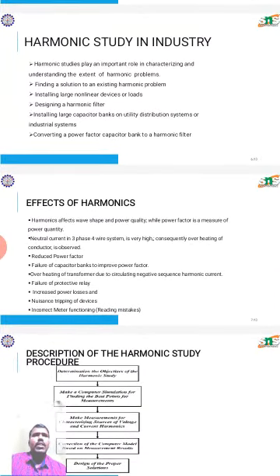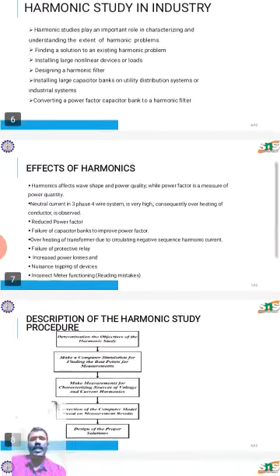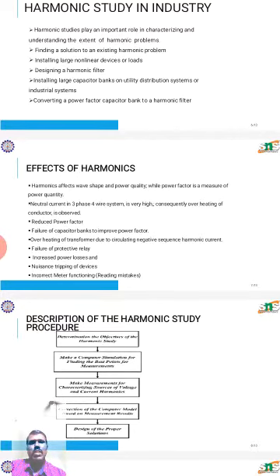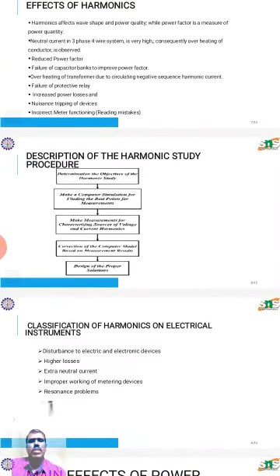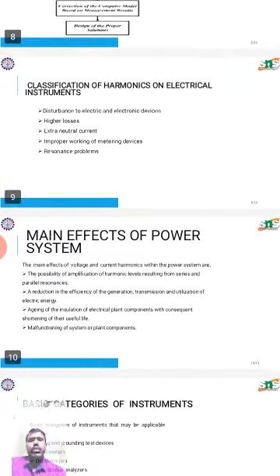Next one, the effects of harmonics on electrical instruments. First one, disturbance of electric and electronic devices. Next, higher losses. Next one, extra neutral current. Next one, improper working of metering devices and resonance problems. Also, the main effects of voltage and current harmonics on the power system are below.